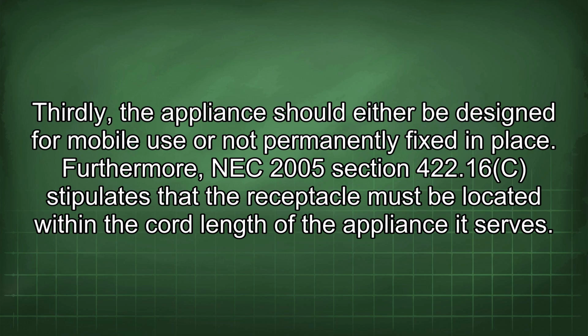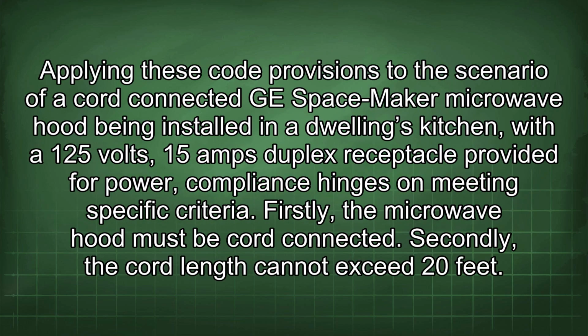Furthermore, NEC 2005 Section 422.16c stipulates that the receptacle must be located within the cord length of the appliance it serves. Applying these code provisions to the scenario of a cord-connected GE Spacemaker microwave hood being installed in a dwelling's kitchen with a 125 volts, 15 amps duplex receptacle provided for power, compliance hinges on meeting specific criteria.